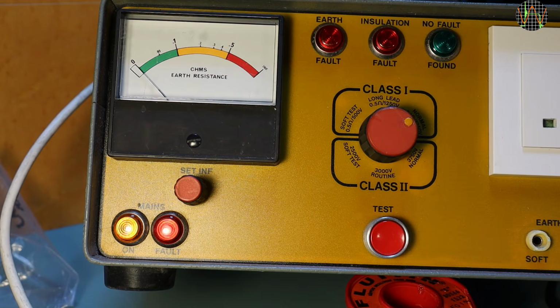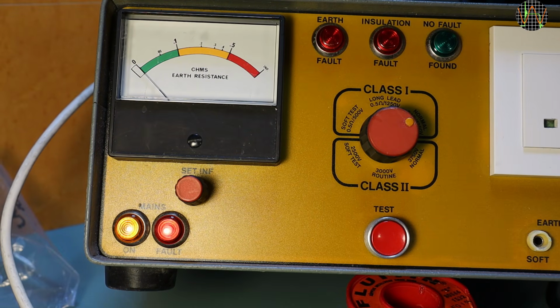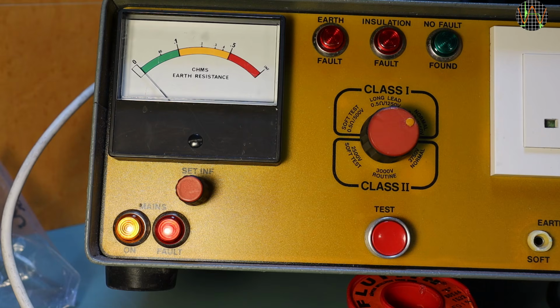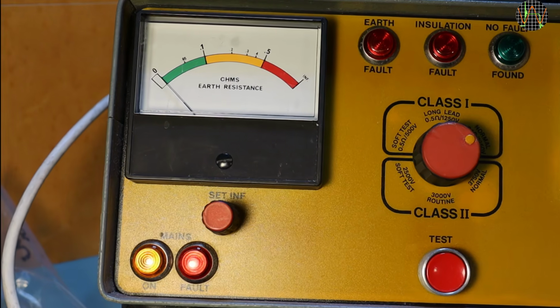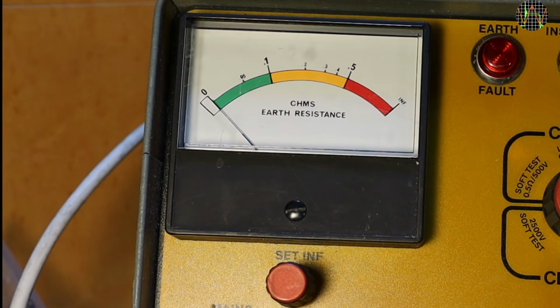As far as operation, there is the rotary button and a push button below that's labeled test. That's it. I suppose the results are shown with the 3 lamps above. 2 red ones if either earth resistance or insulation test failed, and a green one if everything passed. On the most left we have an ohm meter. The green area goes to 0.1 ohm, the orange zone to 0.5 ohm, and everything above 0.5 ohms is red, with the most right position marked inf for infinity. As with most analog multimeters with an ohm range, there is a rotary control marked set inf, where you need to set the instrument to show infinity while no resistance is measured.